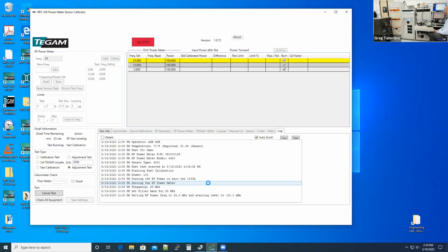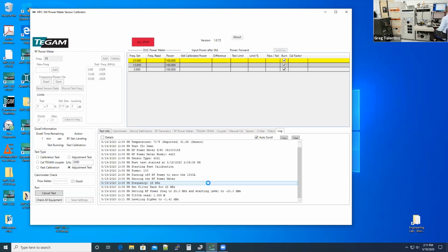While we're waiting, I'll point out that we're using one of our calibrators here. The calorimeter makes a fine water-cooled load. The calorimeter is already indicating 1.35 watts. But the reason we're using the coupler is the calorimeter takes about 6 or 7 minutes to give you a fully settled reading. And you get a fully settled reading from the coupler really within 15 to 20 seconds. It's maybe a little bit too conservative to wait a whole minute.